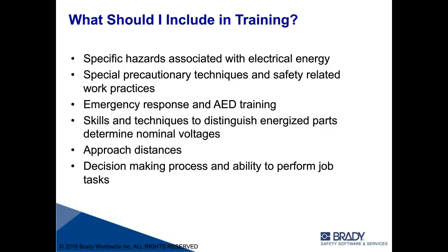The approach distances are very important to include in the training. There are two different types: the limited and restricted approach, which relate specifically to a shock hazard, and the arc flash boundary, the distance at which the incident energy is 1.2 calories per centimeter squared. Training should cover these so guys understand where they have to stand to be safe, and make sure everyone else in the area is safe too.